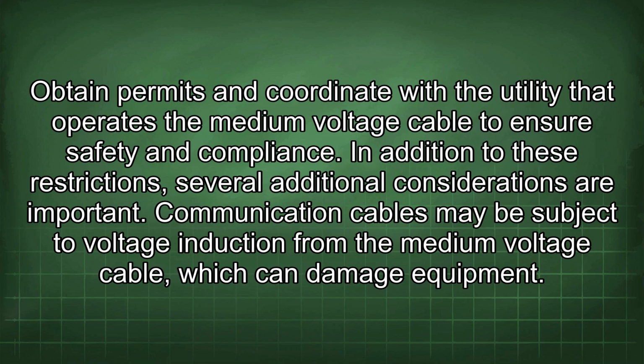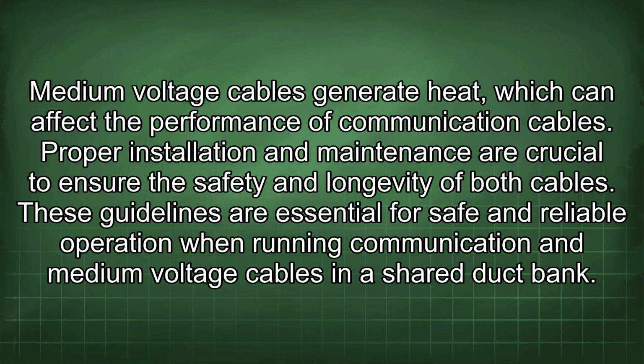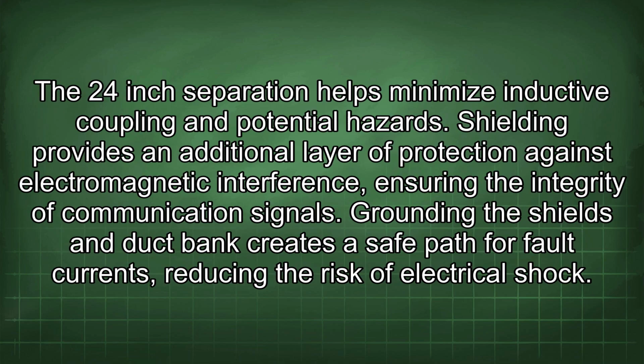Communication cables may be subject to voltage induction from the medium voltage cable, which can damage equipment. Medium voltage cables generate heat, which can affect the performance of communication cables. Proper installation and maintenance are crucial to ensure the safety and longevity of both cables. These guidelines are essential for safe and reliable operation when running communication and medium voltage cables in a shared duct bank. The 24-inch separation helps minimize inductive coupling and potential hazards.